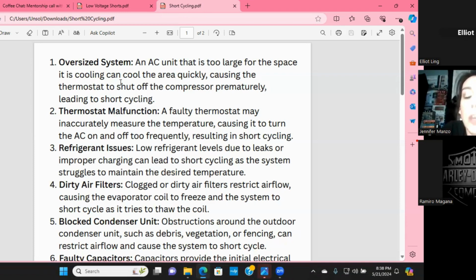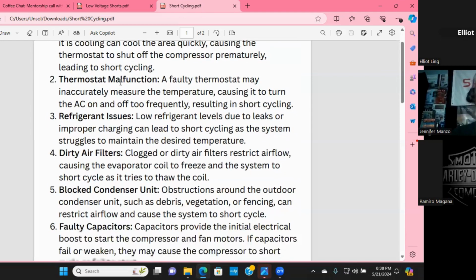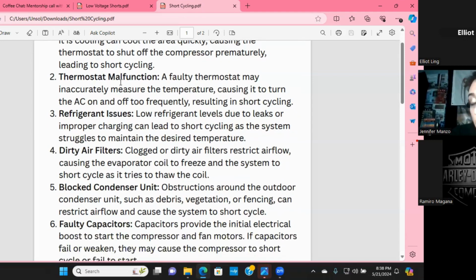So if you go into a house that was built 3 years ago, you may find a properly sized system. Otherwise, you won't. You'll see a horrendously, disgustingly oversized system, undersized or oversized ductwork, and you will see a bunch of flex if you're in the South. Here in the North, we don't really use flex. We use it as it's patented, which is 5 feet to the register and no more. But in the South, they use it for ductwork. And there's nothing wrong with that necessarily, other than you have to really make sure that you're not getting any restrictions and that you're sizing it correctly, because if not, you'll have that short cycling going on in your system. So a thermostat malfunction can obviously cause it, you guys.